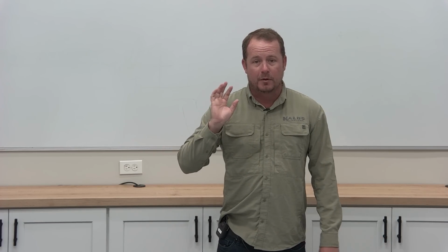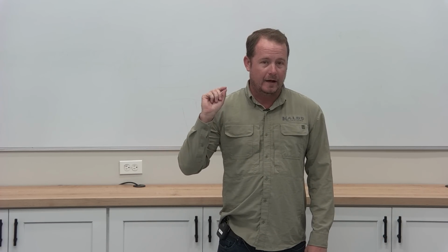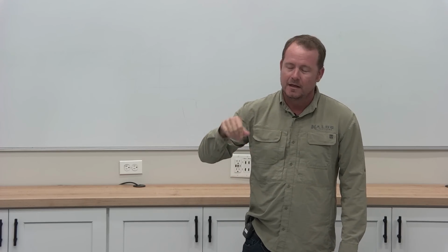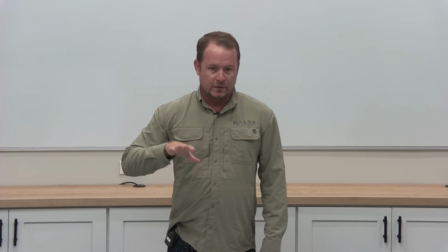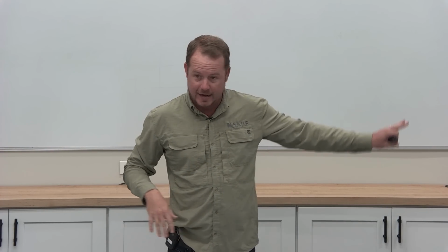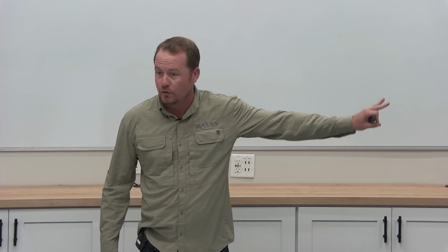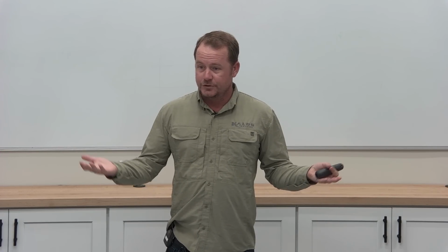I went to a property management house where somebody else converted, it's always somebody else, never us, somebody else converted a gas furnace to a heat pump. So they removed the gas furnace, they put a heat pump in, the water heater was still there. So the water heater still had gas, there was still gas to the house, probably in the stove and other things, right? And what did they do when they disconnected the gas line? Turn it off. You just turn it off, right?